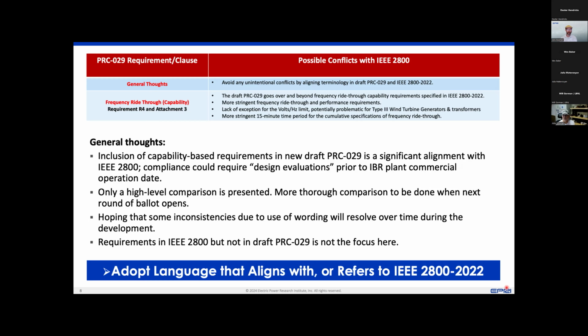So summing this all up, it's important to recognize that the new draft PRC 29 includes capability-based requirements. That seems to be a significant alignment with IEEE 2800 and other capability and performance standards. It also could bring some challenges in how to verify compliance, specifically how the design of an IBR plant could be assessed prior to that IBR plant's commercial operation date.